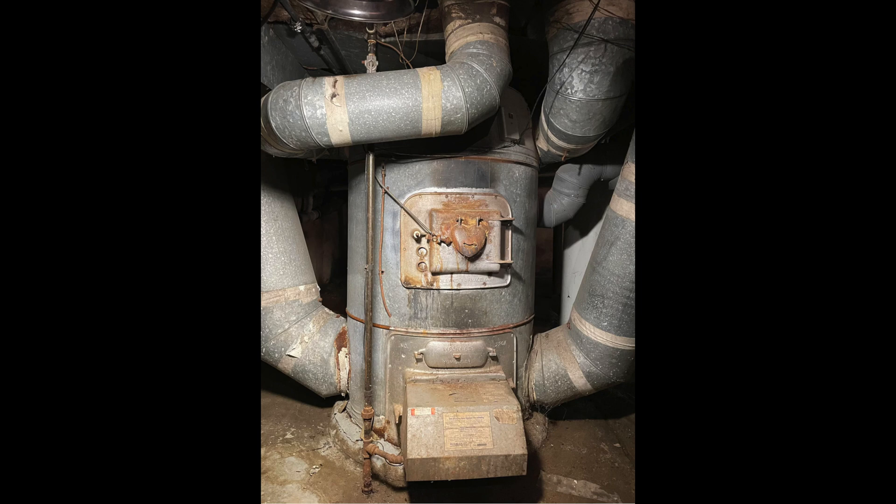The pipes went out to different areas of the house. They usually put the supply in the center of the house, which is kind of opposite of how we do it now, and they put the return air usually somewhere around the front door — towards the outside of the house. It was all natural draft, so it required the heat of the furnace to move the air, and it was eventually just bypassed. There was no way it was going to be a really effective heating system.